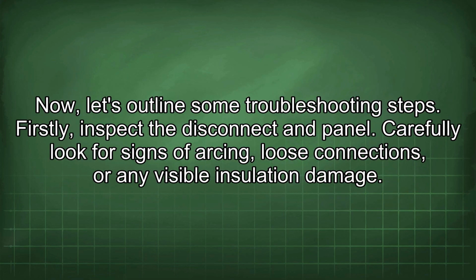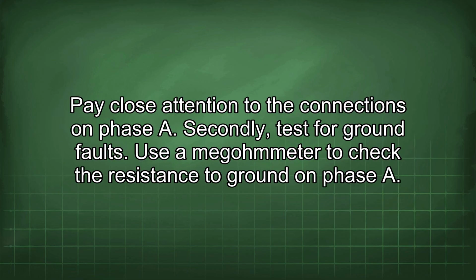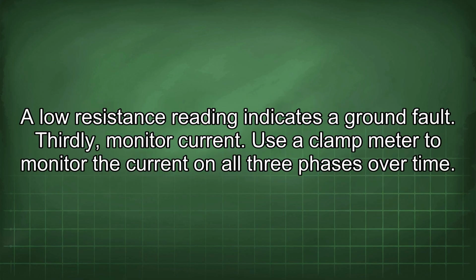Now let's outline some troubleshooting steps. Firstly, inspect the disconnect panel. Carefully look for signs of arcing, loose connections, or any visible insulation damage. Pay close attention to the connections on phase A. Secondly, test for ground faults. Use a megohmmeter to check the resistance to ground on phase A. A low resistance reading indicates a ground fault.